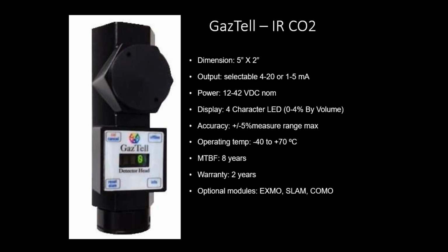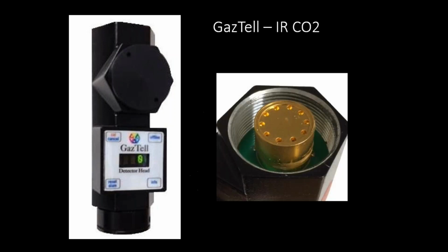And when I say front end, what we're talking about is actually the detector and possibly the light source. The detector on the CO2 is in a wavelength that allows carbon dioxide to absorb that light energy. Whereas if you go back to the GazTell IR for methane, it's using a detector that's set up specifically for the wavelength energy of methane, which would be about 3.3 microns. It too uses the identical optics chamber, which is a gold-plated chamber, very small, and allows the gas to diffuse through the flame arrestor, through the whole optical chamber, and then get to the light source and the detector head so that CO2 can be absorbed.